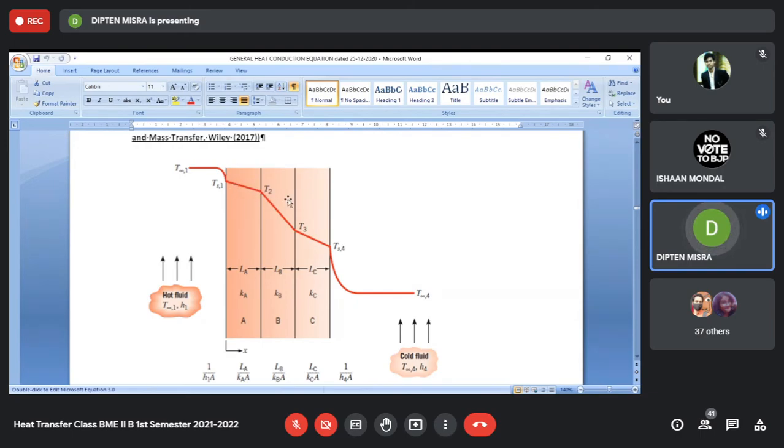then what should be done is that there should be multiple layers. The first layer should be made up of something that can withstand this high temperature. So normally you can use some kind of high temperature resistant, high temperature withstanding material. Normally it may be made up of refractory bricks. Then they may not have sufficient insulating capacity.